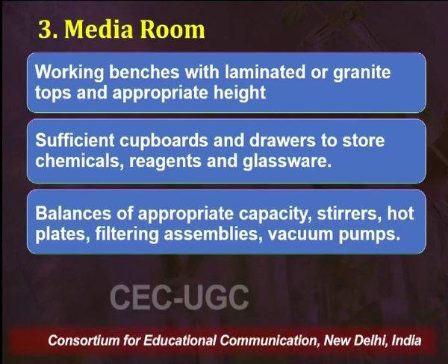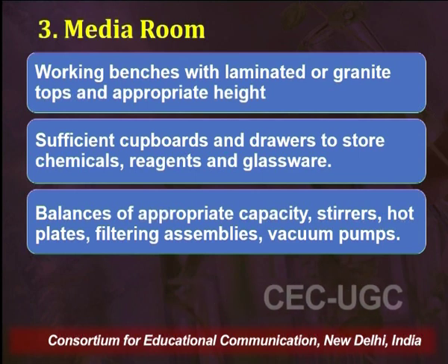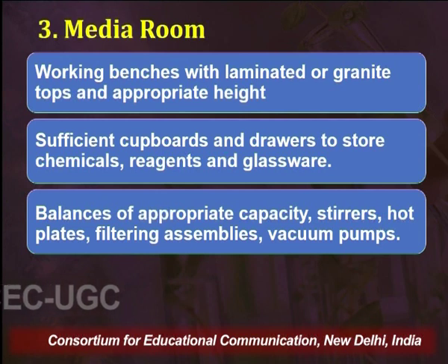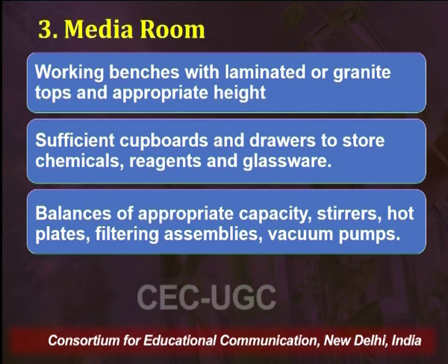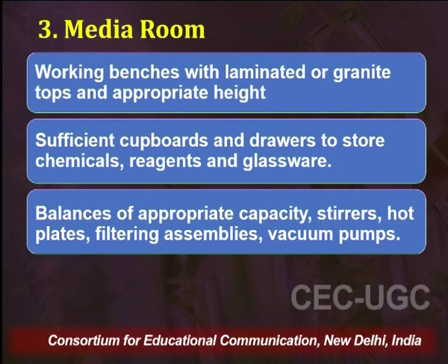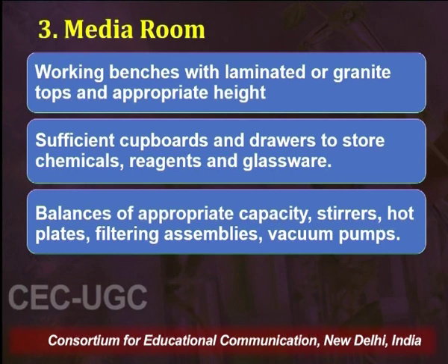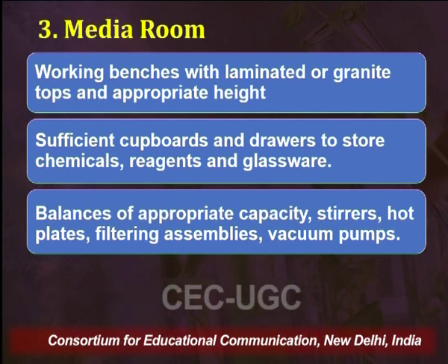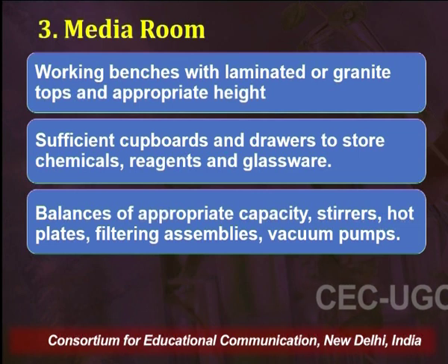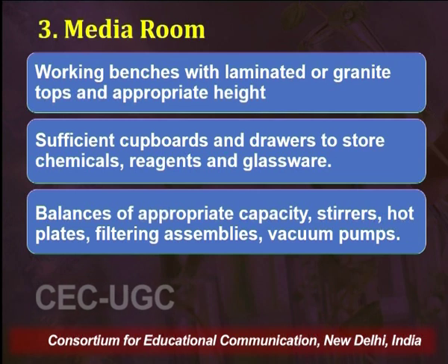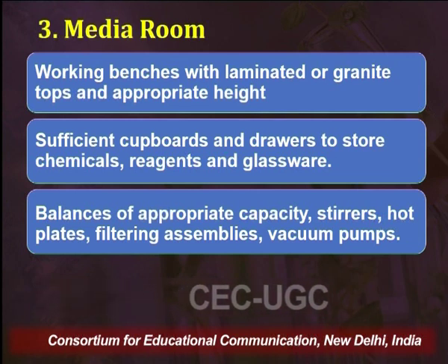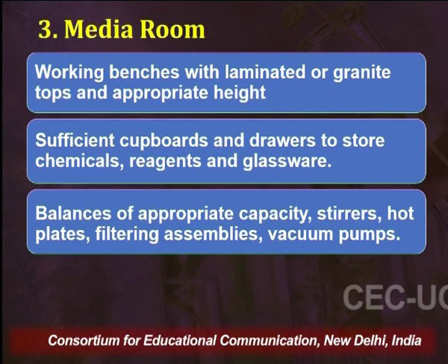Then, since we have to weigh minute amounts of amino acids, growth regulators or any kind of salt for inorganic material, we require balances. So, the media room should always be equipped with fine balances having a minimum weighing capacity of 0.01 gram. Along with balances, the media room should always be equipped with magnetic stirrers or other stirrers in order to mix the contents of the media properly.